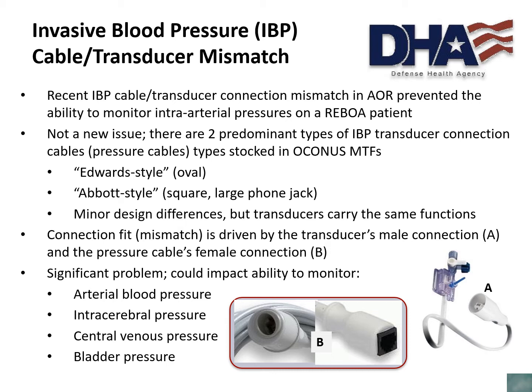The connection fit, or the mismatch, is driven by the male connection on the transducer, indicated by A, and the female end of the pressure cable, which is indicated by B. When the two ends don't fit, this is a significant problem when transferring patients. This could impact the ability to continue to monitor arterial blood pressures, such as in this particular instance, ICPs, CVPs, and also bladder pressures.